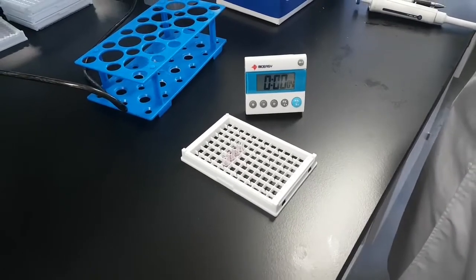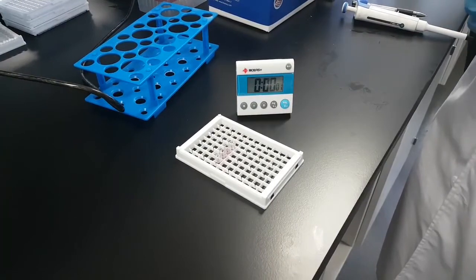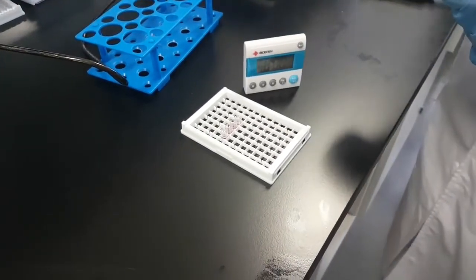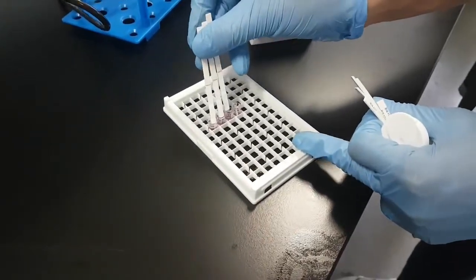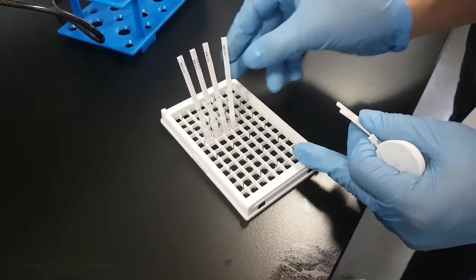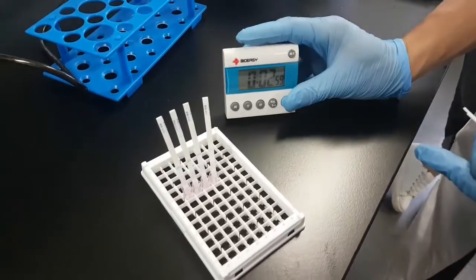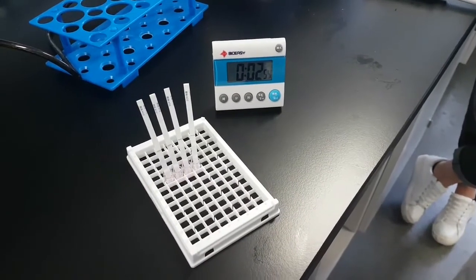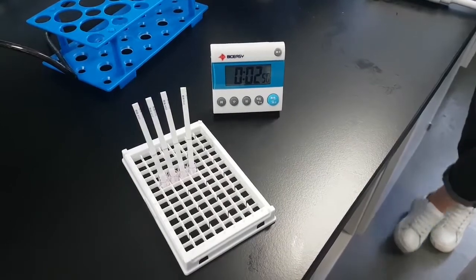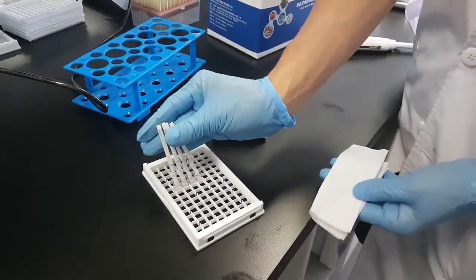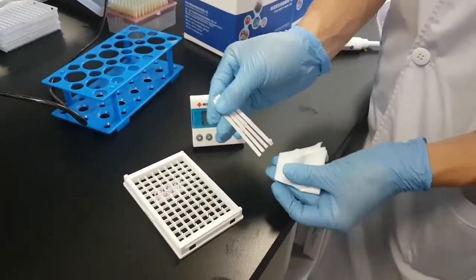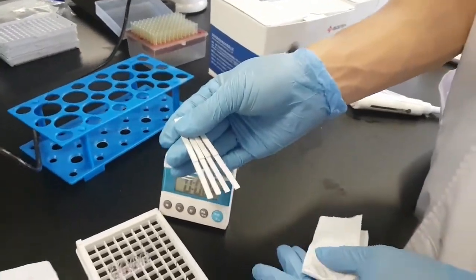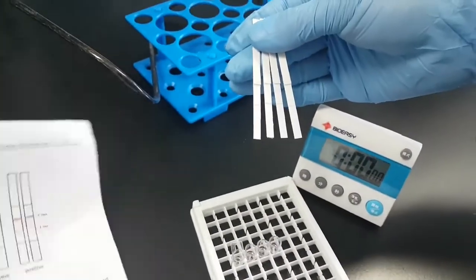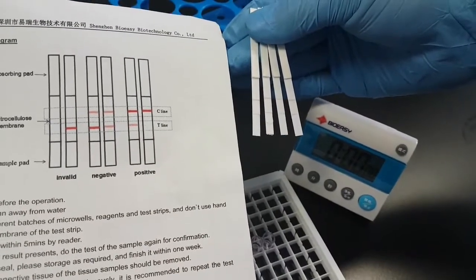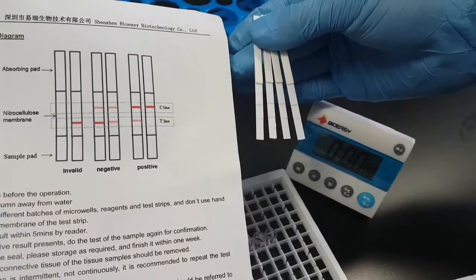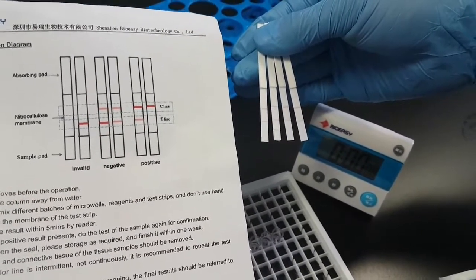Alright, so the first incubation is about to finish. We prepare our test strips. Place our test strips and incubate for another 3 minutes. And again, if the temperature is below 20 degrees, please use the Bioeasy incubator. Second incubation has finished. Now we remove the sample pads. First thing to do is compare the results to the manual. So we can see the result is negative. That was observation by eye, and the next step will be observation by reader.